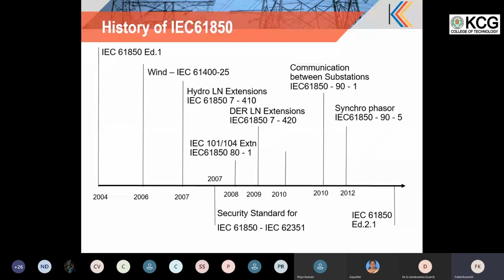Then edition 2 and edition 2.1 of the 61850 standard. They raised an issue, that is technical issues, in a public forum where everybody can post. That was one of the key scenarios for getting the standard popularized. A lot of issues were posted, and they answered with a temporary solution, then incorporated every tissue and released edition 2 of the 61850 standard with all the scenarios included, and this became widely popularized. It is replacing almost every protocol in the new substations. 61850 is getting implemented everywhere.